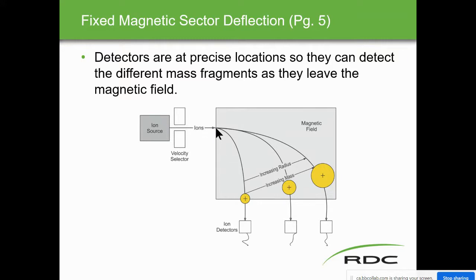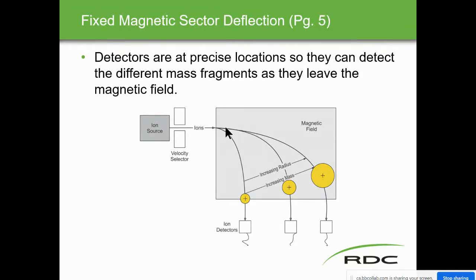Moving to the mass analyzer on page five: the mass analyzer sorts the ions according to mass and sends them to the detector. The three methods are: fixed magnetic sector deflection, variable magnetic sector deflection, and quadrupole mass filter. There is also a fourth method — time of flight. These are the methods used to sort ions, and we'll talk about each one.